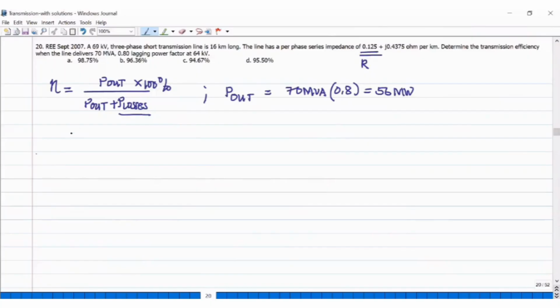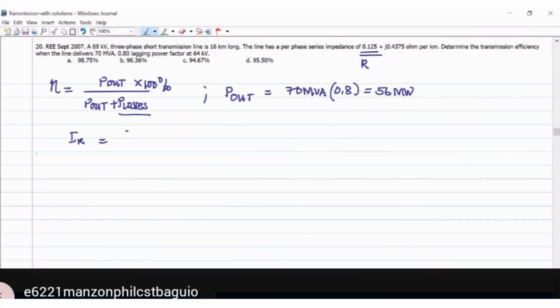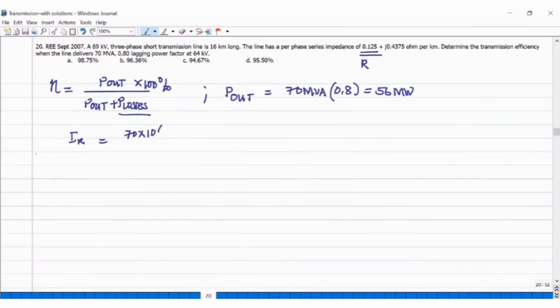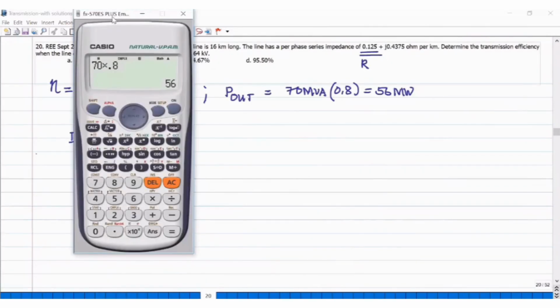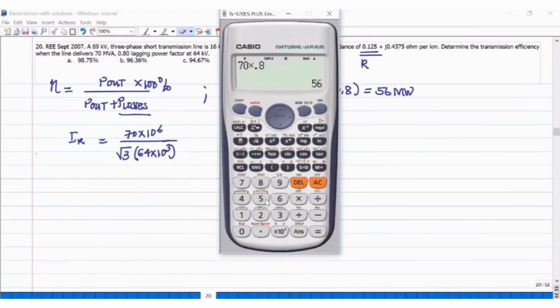Tapos, kunin nyo yung current na dumaan dyan, which is 70 times 10 to the 6 divided by square root of 3. Although the rating of the transmission line is 69 kV, doon sa load, 64 lang siya. So, ang gagamitin natin yung 64 kV. Yun lang yung pangalan ng transmission line, 69. Wala nang power factor. Magnitude lang, kaya hindi natin kailangang i-divide ng 0.8. Doon sa load tayo yon.